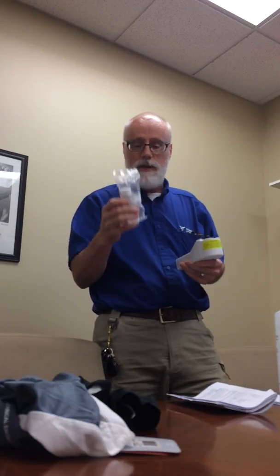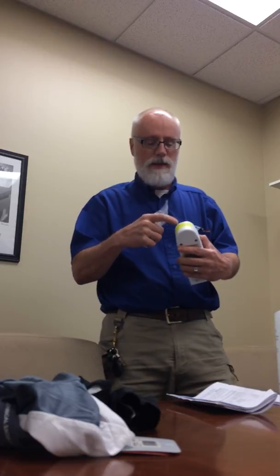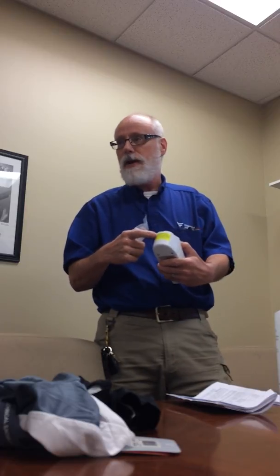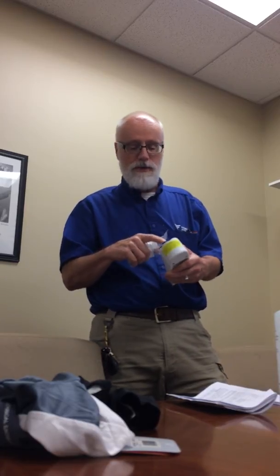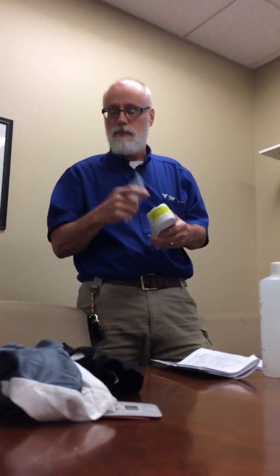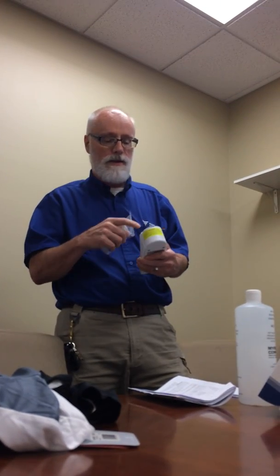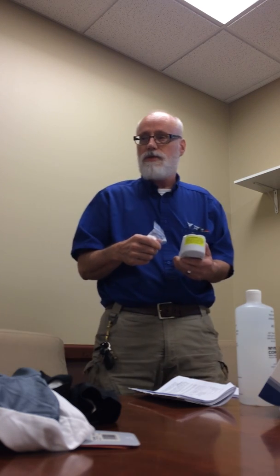Rinse it out with water, and finally in between usage, if it's 30 minutes or greater, they need to fill this. That's why you put the sticker on there, to remind them that if they don't fill this sensor cell with the pH solution, it can damage the sensor, and the meter can be no good and need repair.